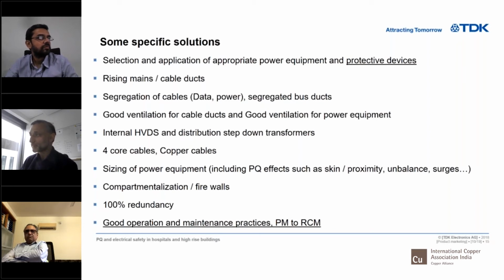Other one is the sizing of the power equipment, not just the normal sizing, because all the electrical power equipment, the transformer, the motor, the switchgear, even the energy meters, are designed on a basic design from 100 years back, which assumes two things: that I'll have a sinusoidal excitation and it will be a balanced 3-phase. Today, neither is the excitation sinusoidal, nor is it a balanced 3-phase. So all the sizing of power equipment, including the design, should consider a very high level of unbalanced sequence components and non-sinusoidal excitation. Then one very important thing is compartmentalization and firewalls.